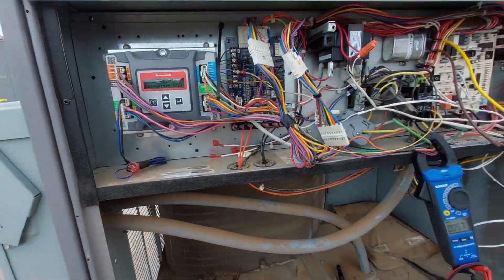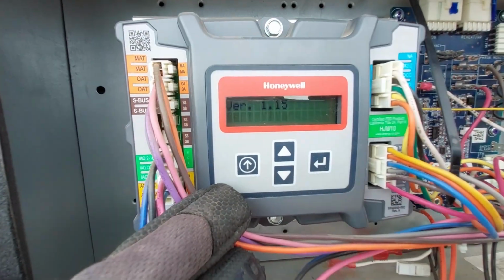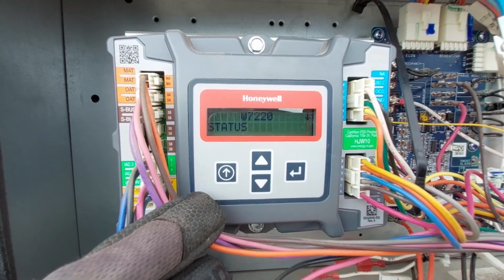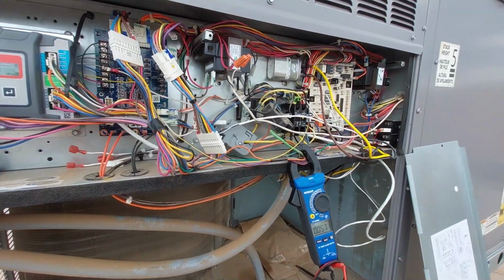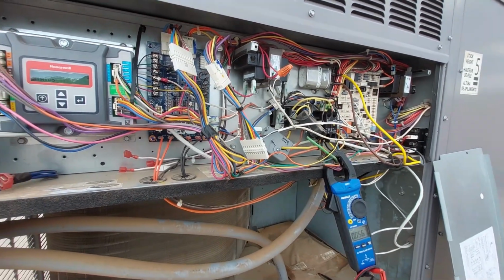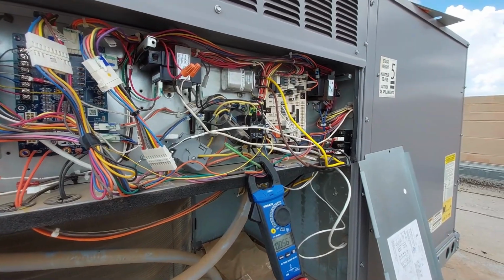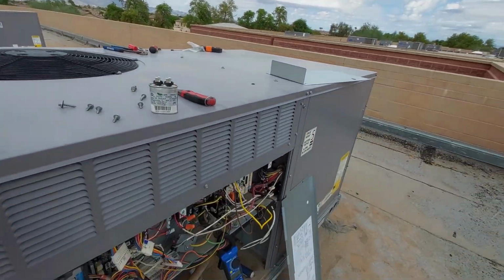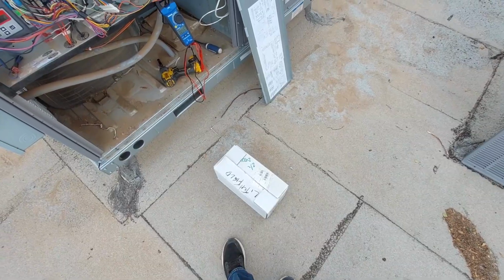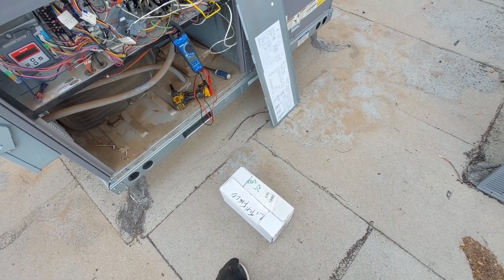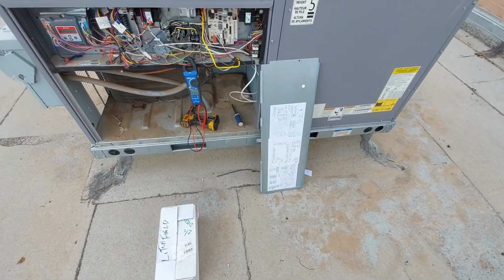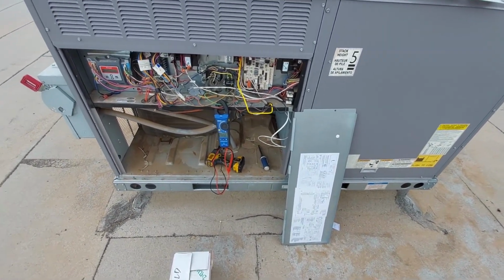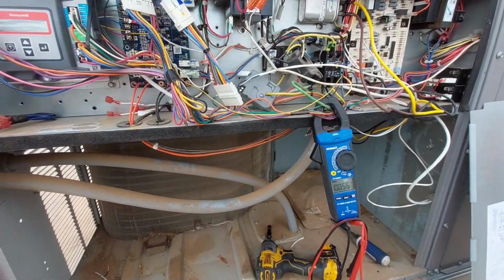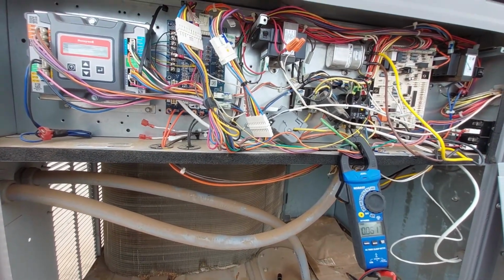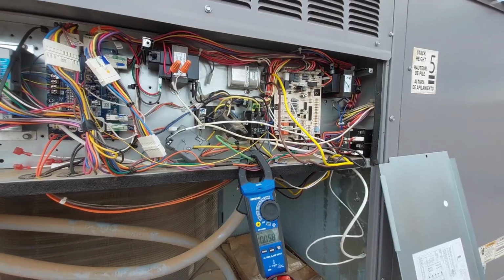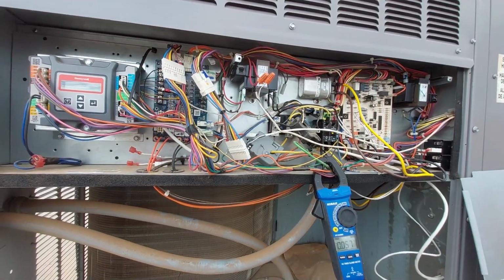So I just turned on the disconnect, but to show you guys, it's running, it's on, but I just cannot get that condenser fan motor to run for some reason. And I don't think it's bad, because I did hook up a brand new one, and the brand new one didn't even turn on. So yeah, this is where I'm at. I'm stuck, you know? You don't know what you don't know.